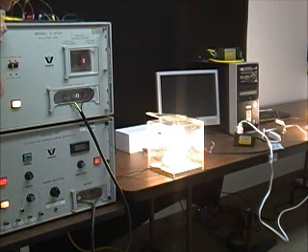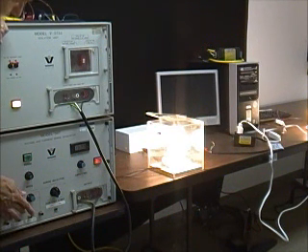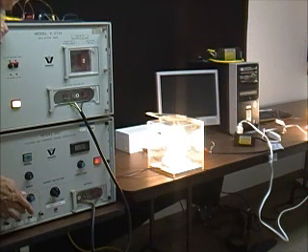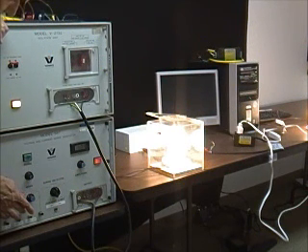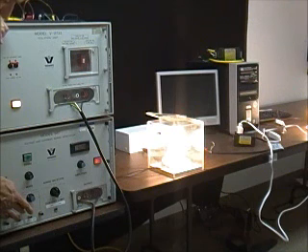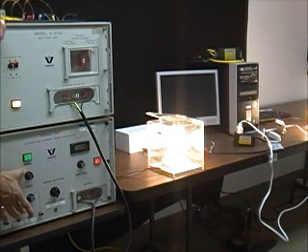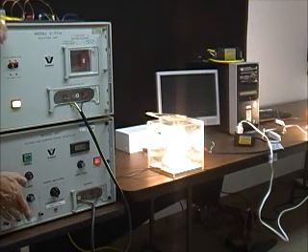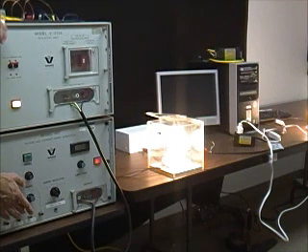Generator charging again. Third impulse. Still protected by the downstream suppressor. Charging again. Ready to test. Fourth impulse, still protected.